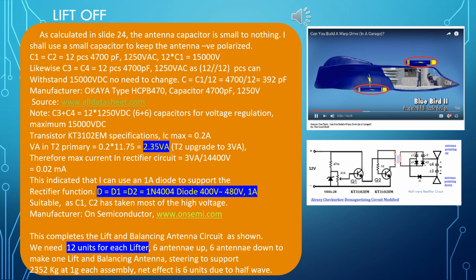Likewise, C3 equals C4 equals 12 pieces of 4,700 picofarad, 1,250 volt AC, as 12 in parallel can withstand 15,000 volt DC; no need to change. C equals C1 divided by 12, equals 4,700 divided by 12, equals 392 picofarad.